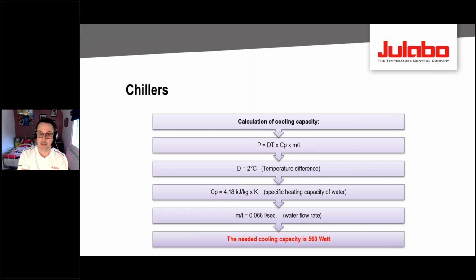The power required - you can see in the second box - is change in temperature times CP, which is heat capacity, times mass, which is your flow rate in kilograms, over time, and that gives you a power figure. In this case, which we calculated for a client, we have a delta T of 2 degrees through the condenser, a heat capacity of water of roughly 4.2, and a flow rate of 0.06 liters per second. From that we get a capacity of 580 watts - that's how much cooling you would require.